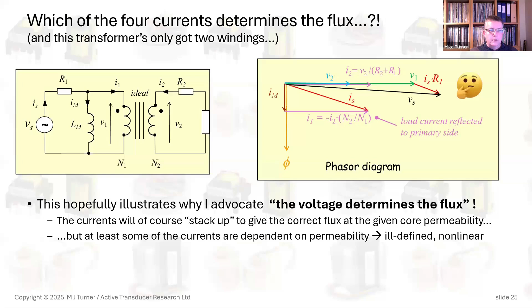If you want to work from current, well, a combination of them does work, and you can work it out that way if you really want to, but you'll need to know the permeability of the core and how it saturates and so on. Whereas if you work from voltage, you just need to know either the primary or the secondary voltage, and possibly the drops across one of the impedances. So a much easier way of working, and that's why I would always say, if you can, work from voltage. There are instances where that's not possible, where the transformer is fed with current, and we'll come across a couple of those a bit later on.